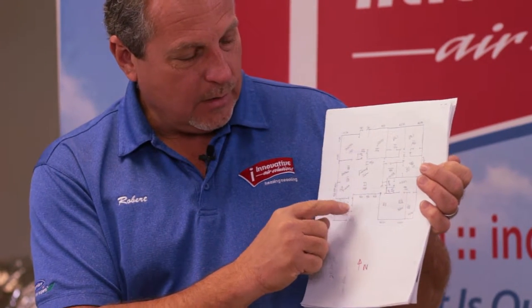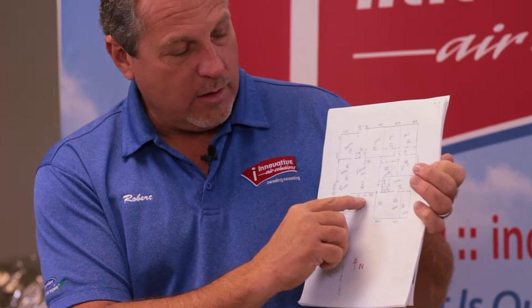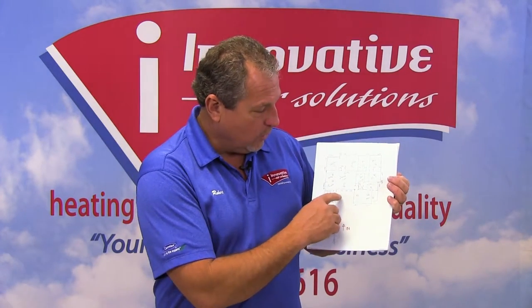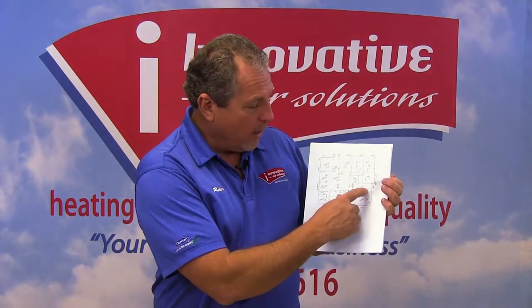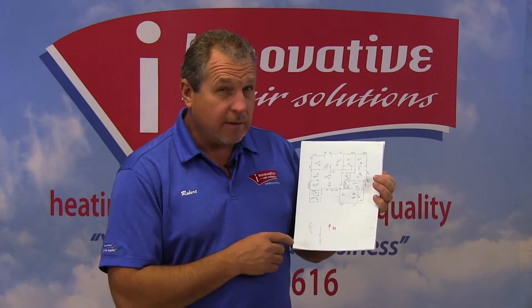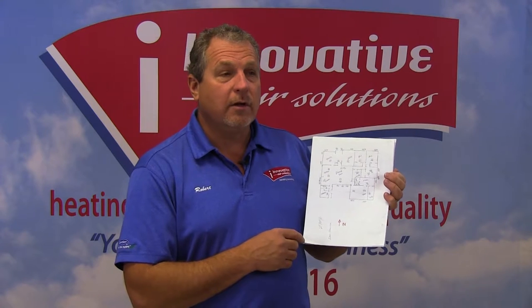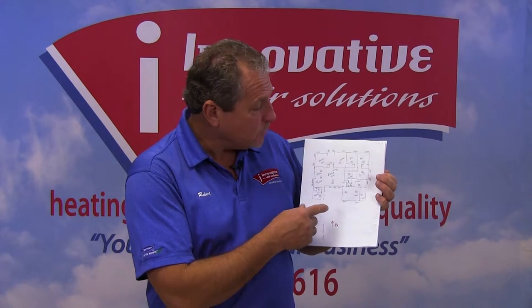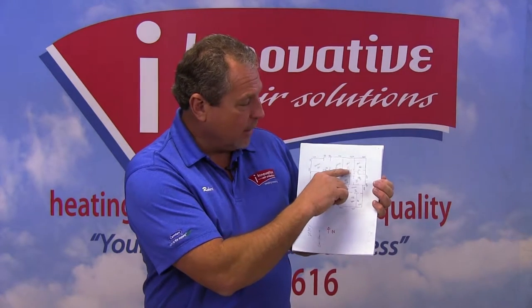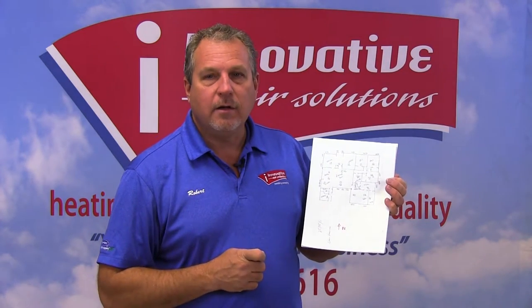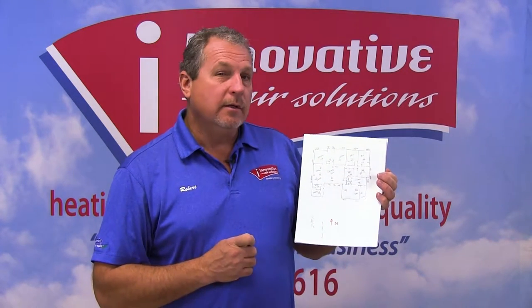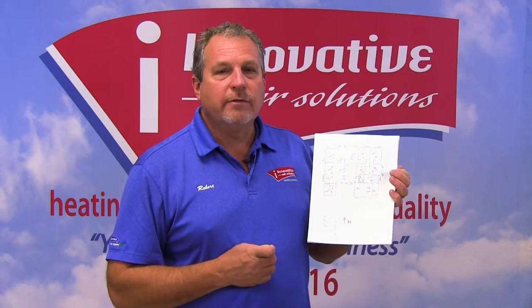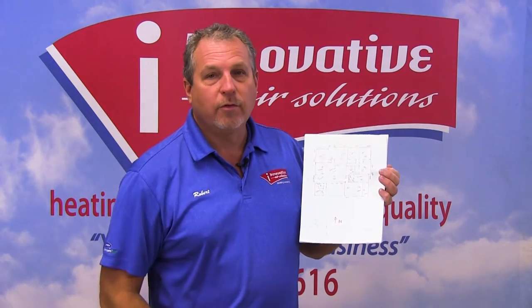I know where my doorway openings are. On the outside, I have all of my window sizes. In this particular house, everything was double pane windows. I also have doorway openings from room to room, which don't really affect a whole lot of the heat load, but if we're going to do a scale drawing, let's get it as accurate as we can. Ceiling heights throughout this home were nine foot. Inside each room, I have noted the size of the duct opening — for example, a 14 by 6 grill, 10 by 6, 8 by 4 — because I know certain values of air I'll actually be able to move through each grill size.